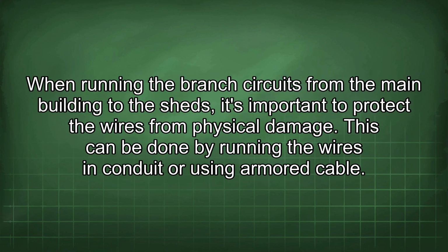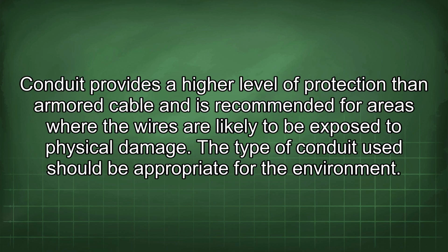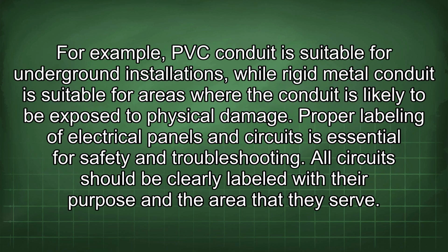When running the branch circuits from the main building to the sheds, it's important to protect the wires from physical damage. This can be done by running the wires in conduit or using armored cable. Conduit provides a higher level of protection than armored cable and is recommended for areas where the wires are likely to be exposed to physical damage. The type of conduit used should be appropriate for the environment. For example, PVC conduit is suitable for underground installations, while rigid metal conduit is suitable for areas where the conduit is likely to be exposed to physical damage.